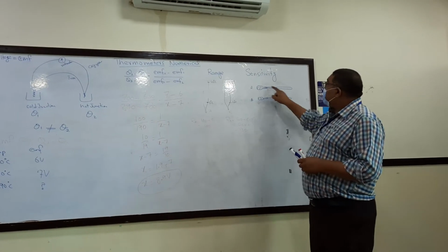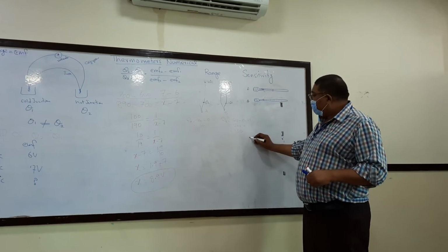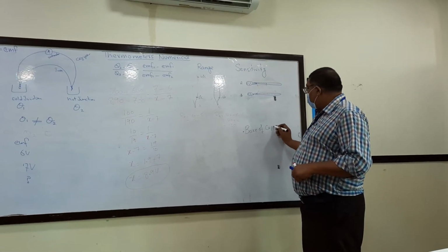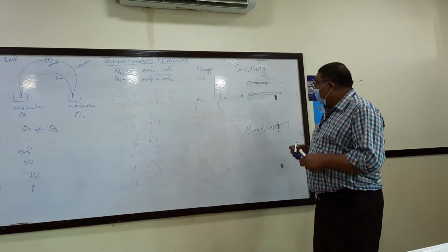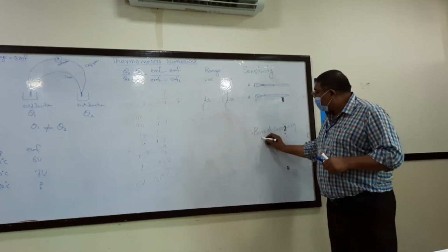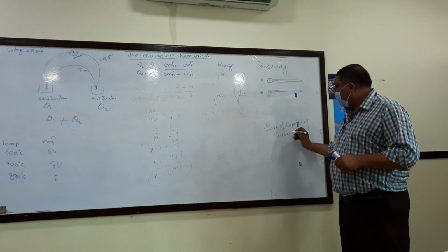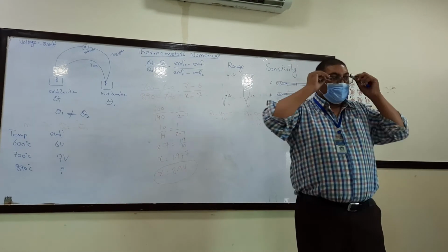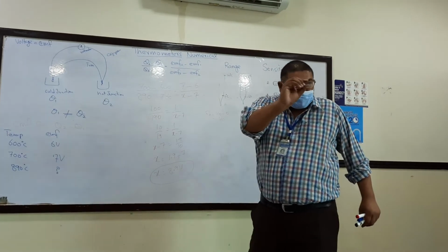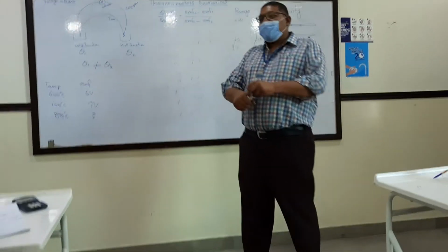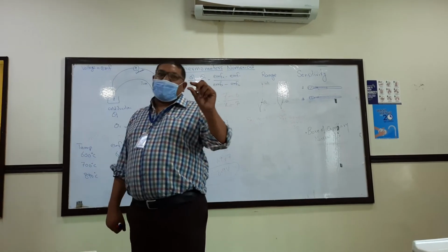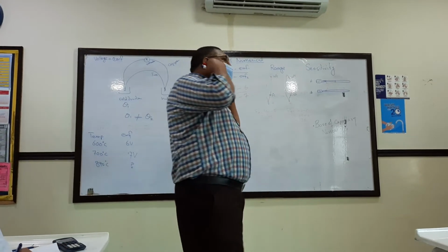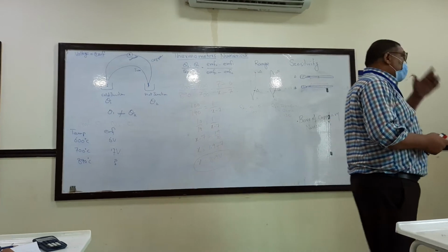You see, this capillary, the one method is the bore of the capillary. The bore of the capillary should be narrow. The diameter of that bore, this capillary in which that mercury column travels, should be very small. The thermometers which have a smaller capillary bore will be more sensitive, because in them the mercury will travel a longer length.